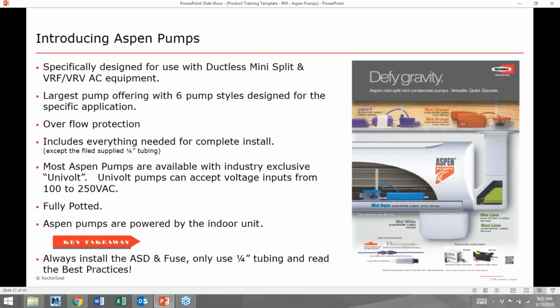And another key takeaway for today is talking about our best practices. We'll touch on that a little more at the end. But if you take anything away today, when someone asks you about installing the pump, you want to tell them to always install the ASD, the anti-siphon device, install the fuse link, which are both included in the box, and only ever use 1/4-inch ID tubing. All of these things are mentioned in the best practices.